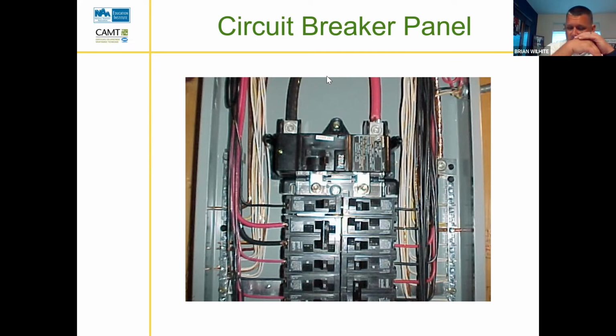However, there are times where one of our legs drops out or goes bad. And so how could I test that? Well, I would go from the black on the top left to a ground. And if that told me 120 volts, then I'd move over to the red. If that one told me 0, then I would know that leg coming in to my breaker box is bad.